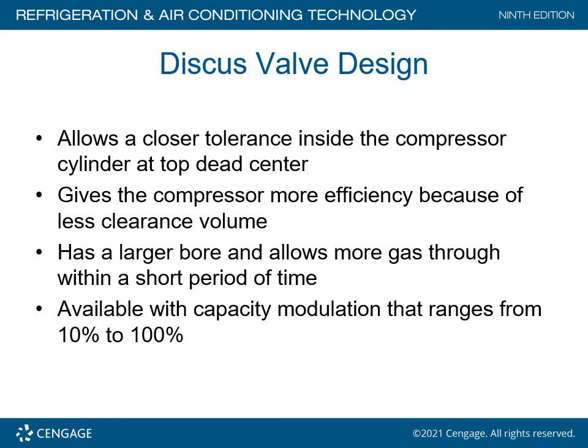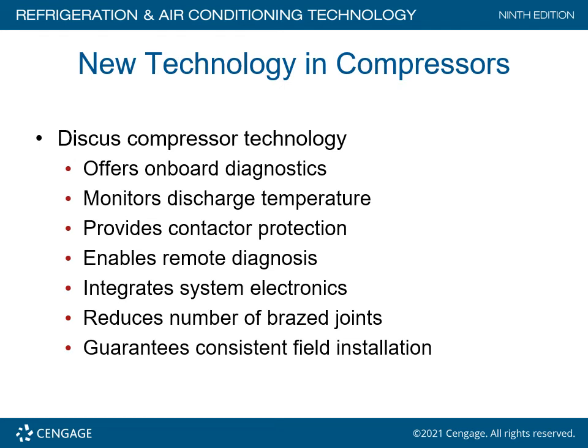The Discus valve design, developed by Copeland Corporation, allows a closer tolerance inside the compressor cylinder at top dead center, giving more efficiency due to less clearance volume. It has a larger bore, allows more gas flow in a short period, and is available with capacity modulation ranging from 10 to 100%. New Discus compressor technology offers onboard diagnostics, monitors discharge temperature, provides contactor protection, enables remote diagnosis, integrates system electronics, reduces brazed joints, and guarantees consistent field installation.